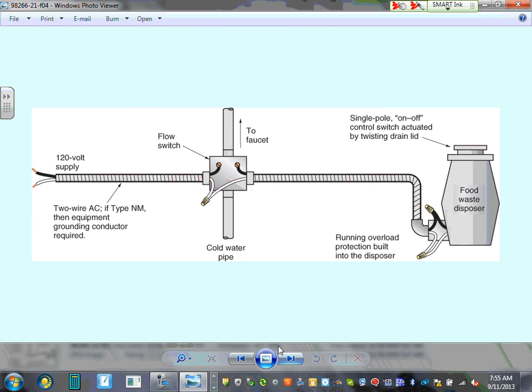Sometimes also, what happens if you run your garbage disposal without water? You'll burn it for a long time, right? So sometimes what they do is they put a flow switch in the pipe. I haven't seen it, but you can put a flow switch. What happens, guys, is when the water starts going through that pipe, it activates the flow switch and it closes this contact. Did you guys use a flow switch? I don't think we have a flow switch in our lab.